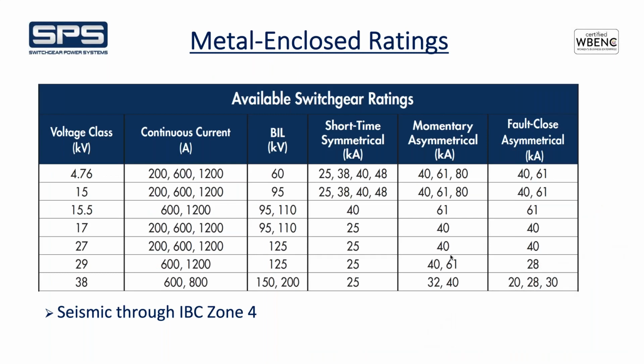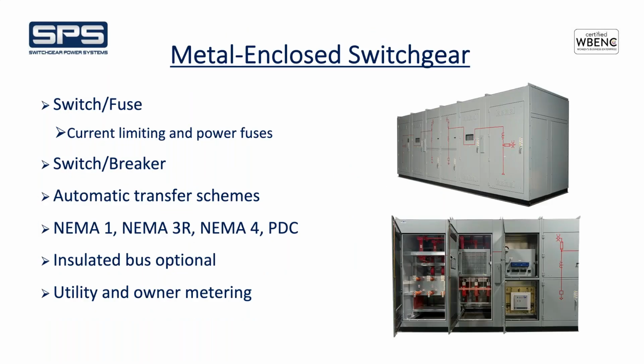So metal enclosed switchgear. This table is focused on what we would call more traditional metal enclosed with switches, sometimes switch breaker combinations, but same as metal clad, we build 5 to 38 kV. At 38 kV, we actually now offer up to 1200 amp load break. So switch fuse, switch breaker, I talked about. These two pictures here is a good example of what I will get into in more detail of a fixed mounted circuit breaker at 38 kV in a metal enclosed design. So you have provisions for utility metering, disconnect switch, and then you have your breaker feeding the circuit. And then you can see the single line here represents that.